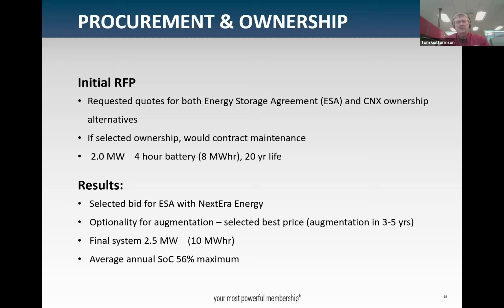We ended up back with NextEra Energy with an energy storage agreement. NextEra owns the battery facility, connects it to our existing substation, and maintains it, while we dispatch it. We went with a slightly bigger system, 2.5 megawatts, to make it more cost effective for them, since a bit bigger size let them use a lot of the standardized equipment and materials they typically use for other installations.